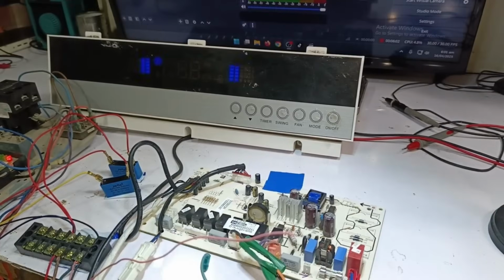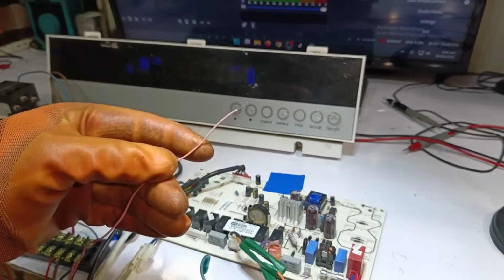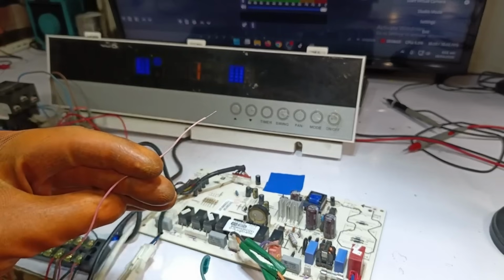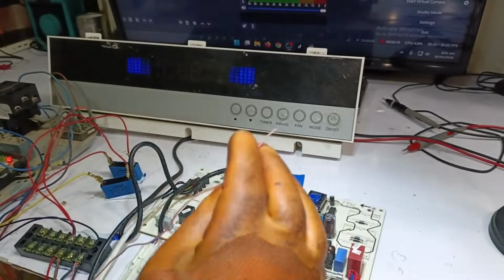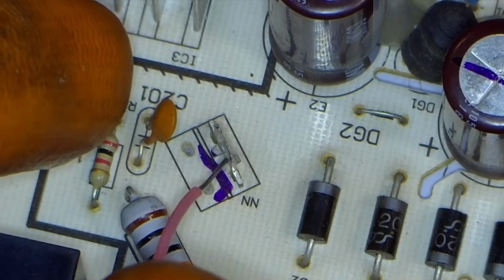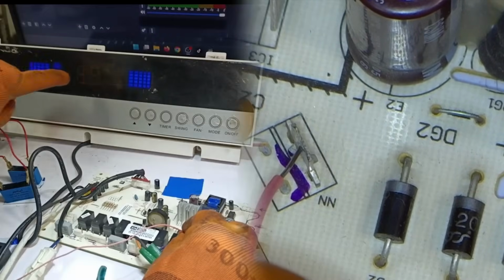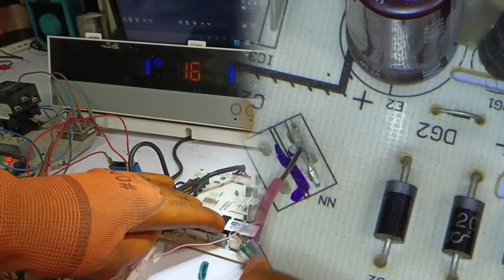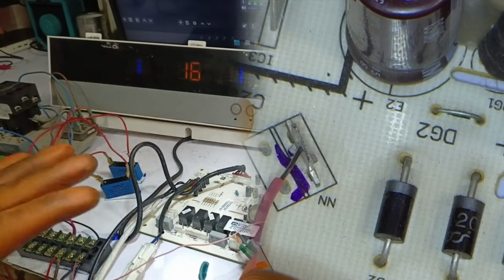Now, how can we eliminate this F1 error? We will check it using the wire we prepared earlier. Remember, this wire was connected to the neutral. Now we will attach this wire to the signal wire, and you will see that the display shows 16 degrees, and one of the relays has also switched. In this way, our system is working perfectly fine. Also, notice that as soon as I removed the wire, the F1 error started showing again.